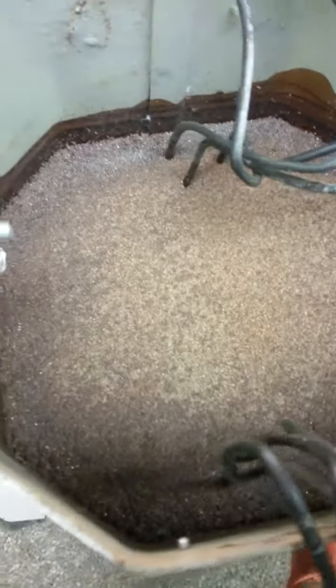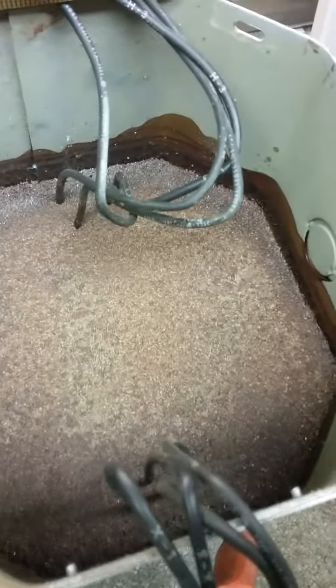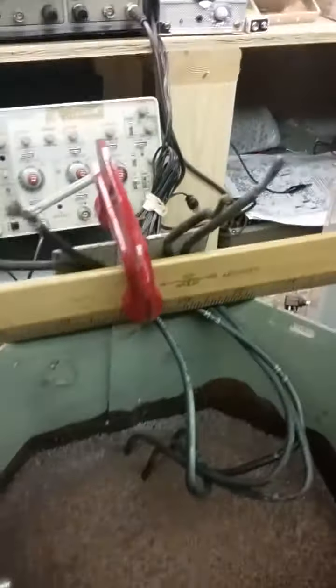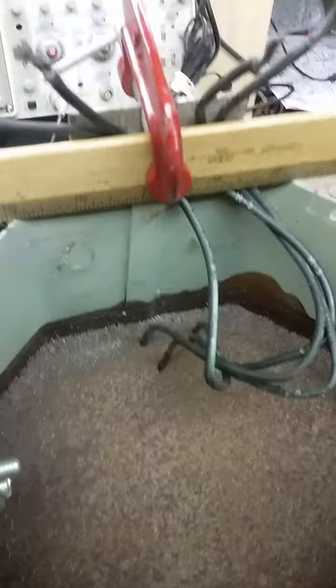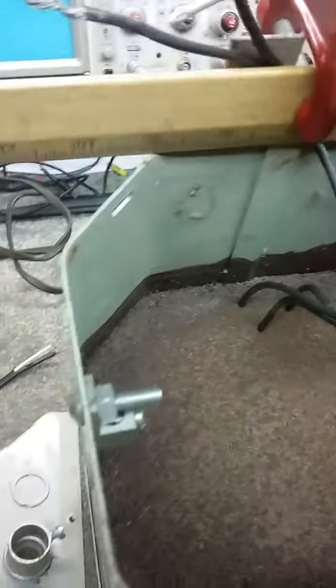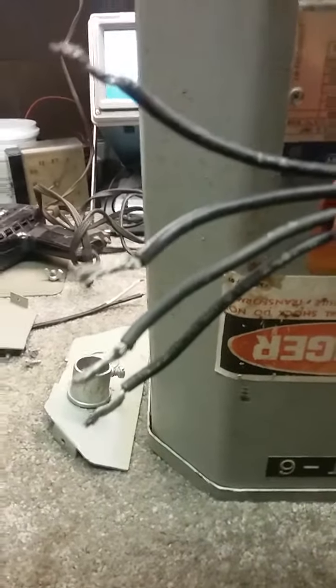This is a resin sealed, I believe resin and sand mix, sealed transformer. So it's made for indoor-outdoor use. Actually, it's made for outdoor use, but of course it works indoors. It has a tab in the front and back, which now that ruler is covering one of them, so you can mount it vertically on a wall or up on a pole. And anyway, here, that's the primary there. These are the secondary. I got them in the same order from top to bottom, 1, 3, 2, and 4.